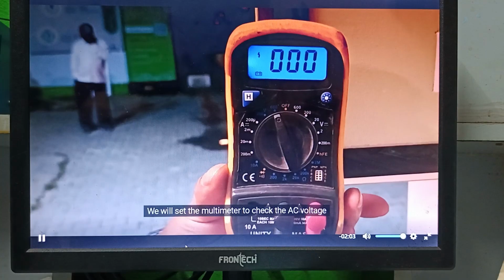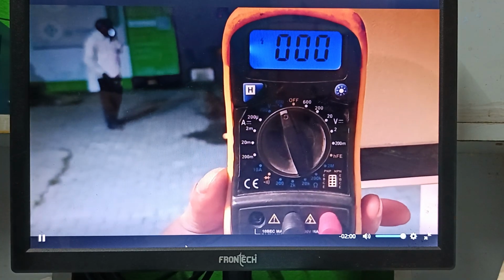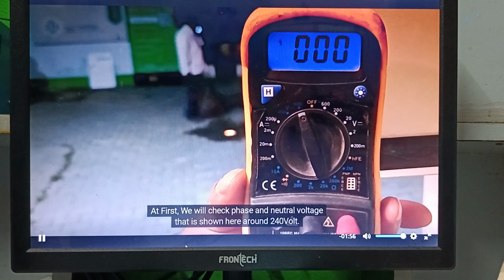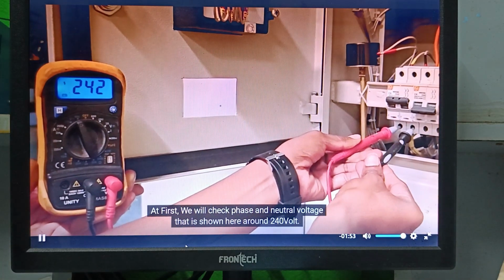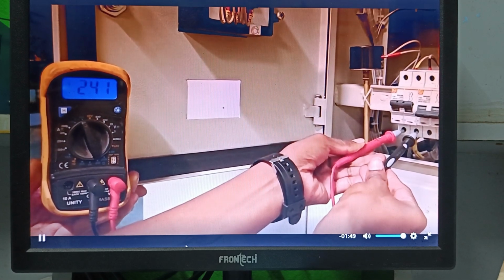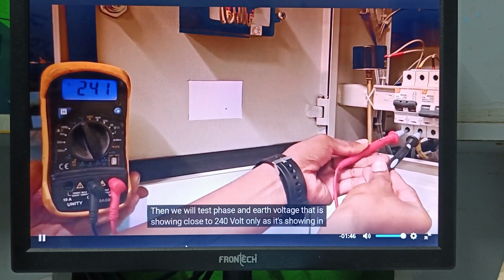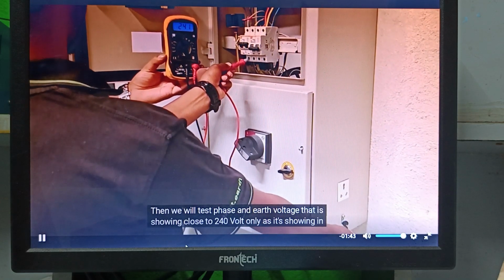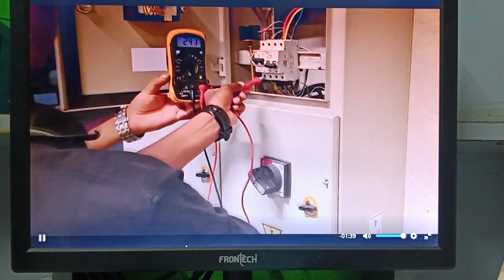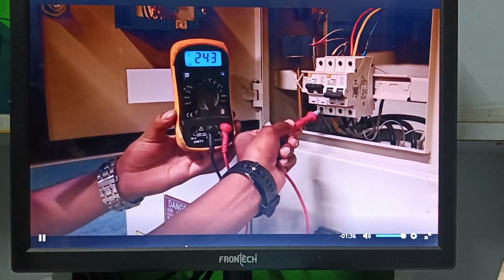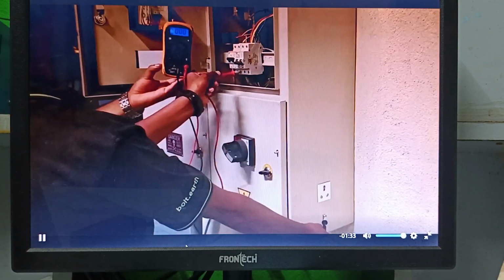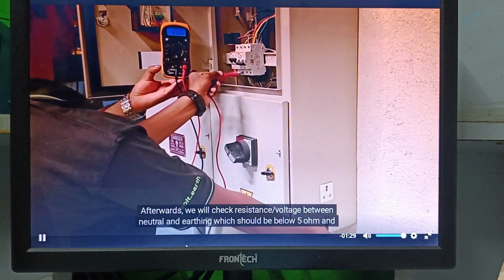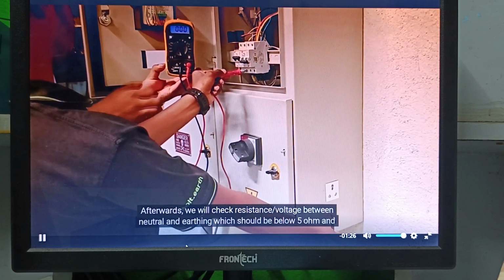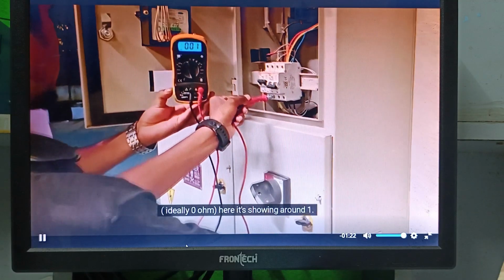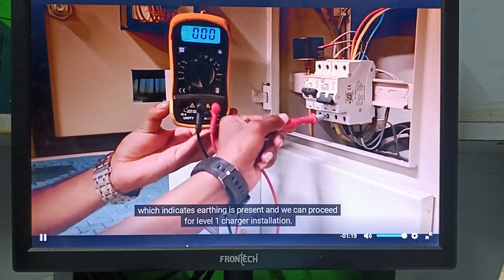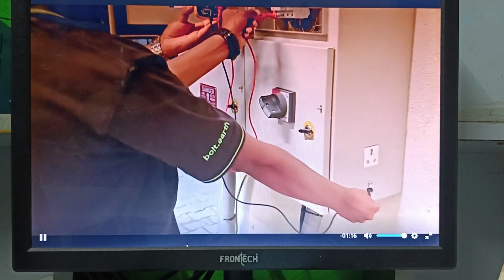We will set the multimeter to check the AC voltage. At first, we will check phase and neutral voltage, which is shown here at around 240 volt. Then we will test phase and earth voltage, which is showing close to 240 volt only, as shown in the multimeter. Afterwards, we will check resistance between neutral and earthing, which should be below 5 ohm and ideally 0 ohm. Here it's showing around 1, which indicates earthing is present and we can proceed with Level 1 charger installation.